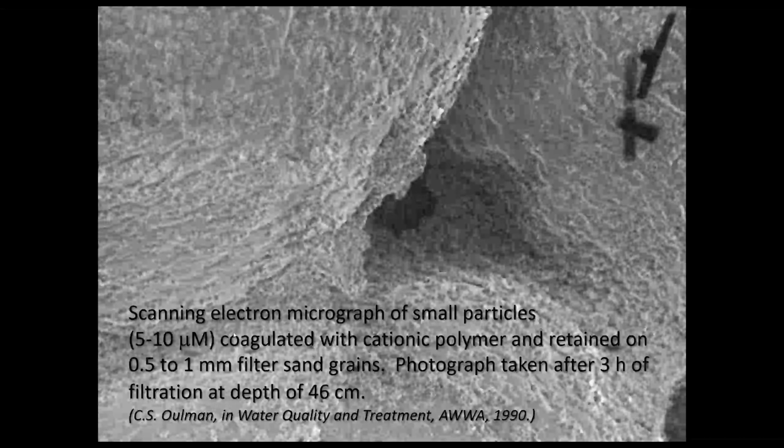Down here in the description, it says that these are small particles coagulated with a cationic polymer, that's our positively charged polymer, and retained on the filter sand grains. This is after 3 hours of filtration at a depth of 46 centimeters.